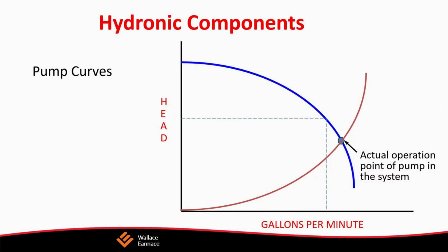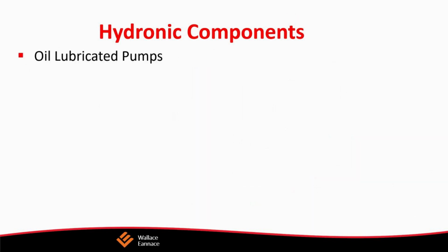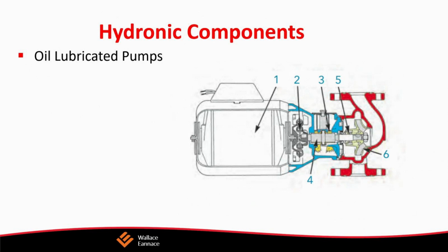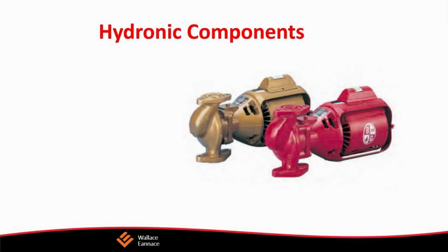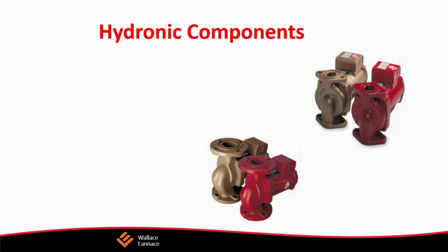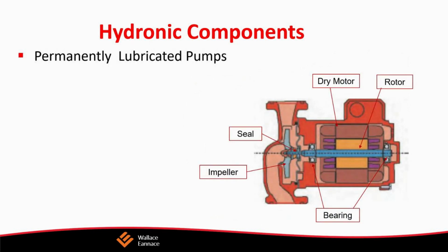So with this example, the pump needs to deliver 2.4 GPM. We had 50 feet of baseboard plus 50 feet of piping, which is 100, plus 50% is 150 feet, times 0.04 is 6 feet of head. And then we got 24,000 BTUs divided by 10,000 is 2.4 GPM. So we need a pump that's going to give us 2.4 GPM at 6 feet of head. Looking at this example, we need something that's going to deliver that. Here's a sample chart. These are from Bell & Gossett's three pumps here, the NRF22, the 33, and the NRF9. We plot that point. You can see we're above the NRF9, but we're below the NRF22 and the NRF33. So we could use either one of those pumps.